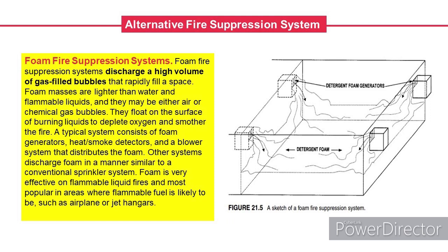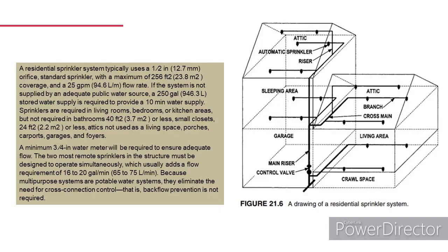A typical system consists of foam generators, heat/smoke detectors, and a blower system that distributes the foam. Other systems discharge foam in a manner similar to a conventional sprinkler system. Foam is very effective on flammable liquid fires and most popular in areas where flammable fuel is likely to be, such as airplane or jet hangars. Here is an example of a diagram.